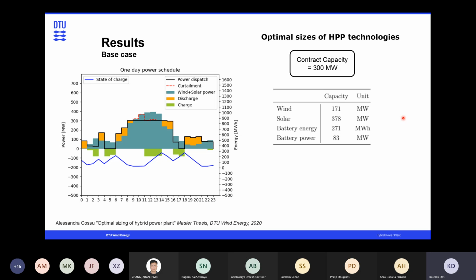When we designed based on this, we found that for a contract capacity, meaning the grid connection capacity given as 300 megawatt, the wind installed capacity should be 171 megawatt, solar 378 megawatt, and battery 80 megawatt with 3-hour storage. Adding them up in terms of power comes to about 630 to 640 megawatt, which is more than 2 times the grid connection capacity.